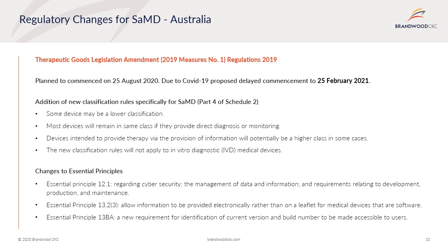The new classification rules will not apply to IVD medical devices. There will also be changes to the essential principles: Essential Principle 12.1 has been amended to clarify expectations around cybersecurity, the management of data and information, and requirements relating to development, production, and maintenance. Essential Principle 13.2 has been amended to allow information to be provided electronically rather than on a leaflet for medical devices that are software. A new requirement, Essential Principle 13BA, has been introduced for identification of the current version and build number to be accessible and identifiable to users of medical devices that are or incorporate software.